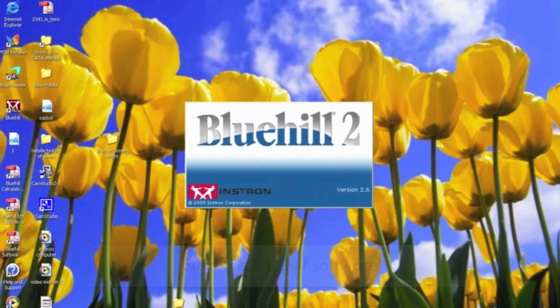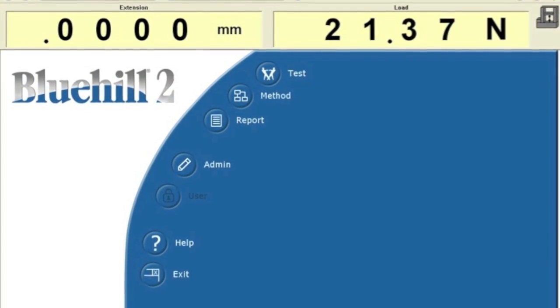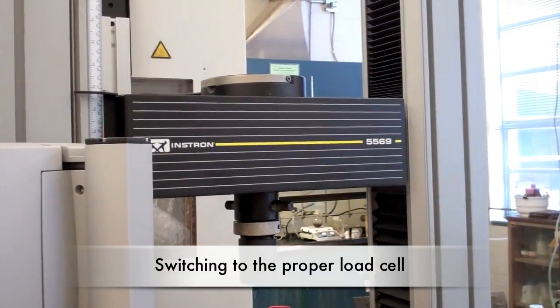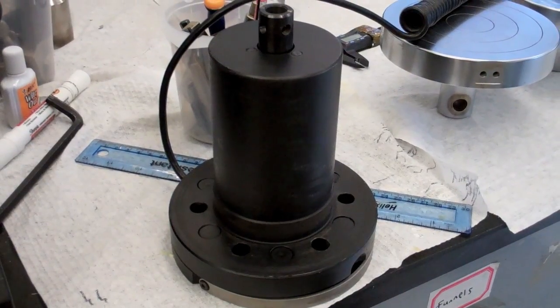Double-click on the Bluehill icon to start the software. The software shows the extension and load at the top. First, you need to choose the proper load cell. There are 2 kN and 5 kN load cells that are chosen depending on the load range and sensitivity of the sample.